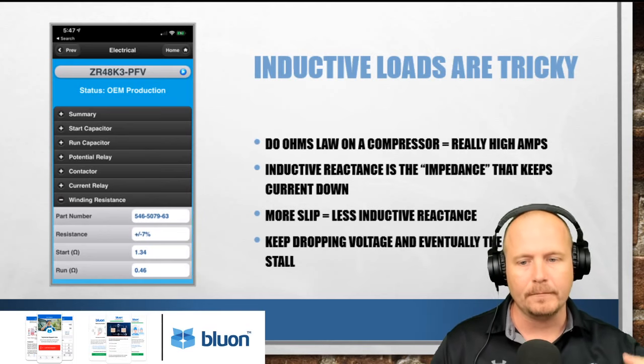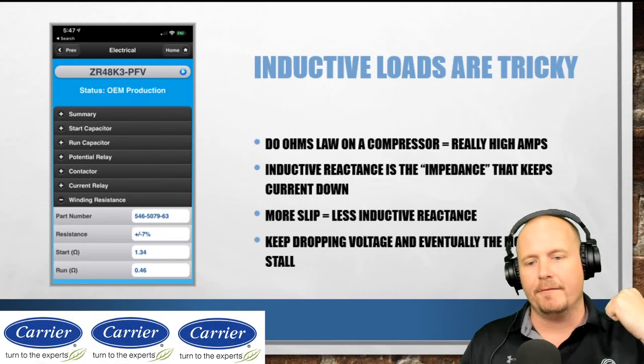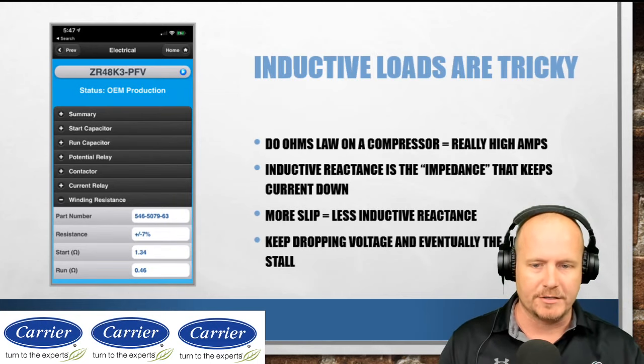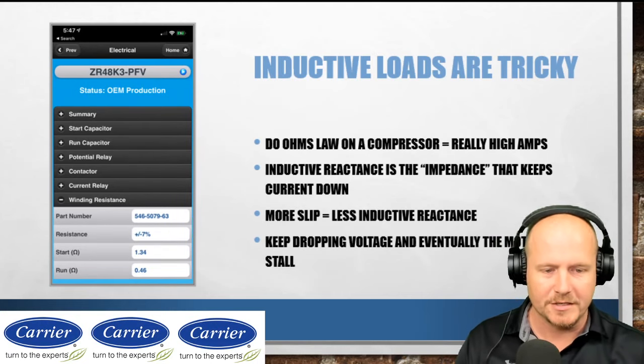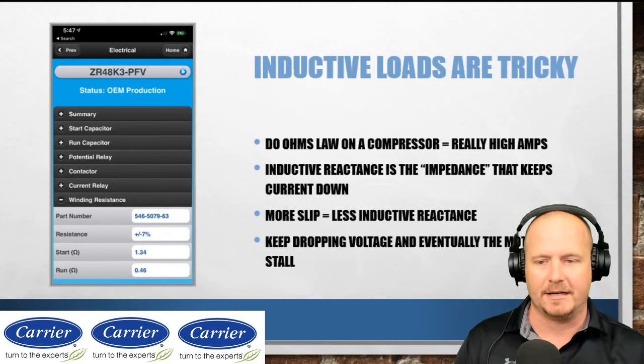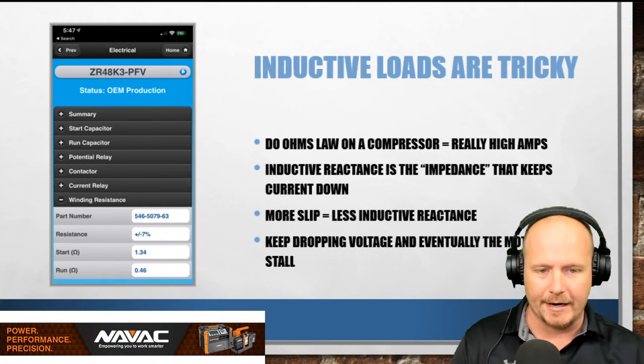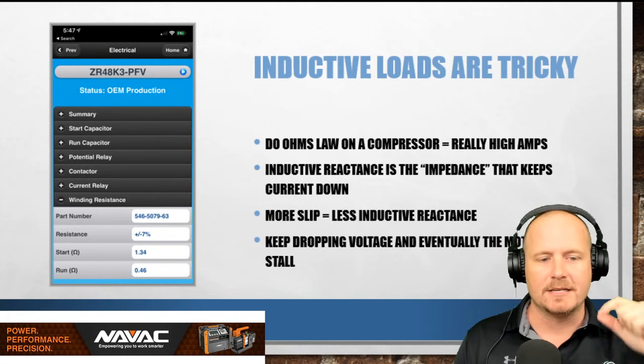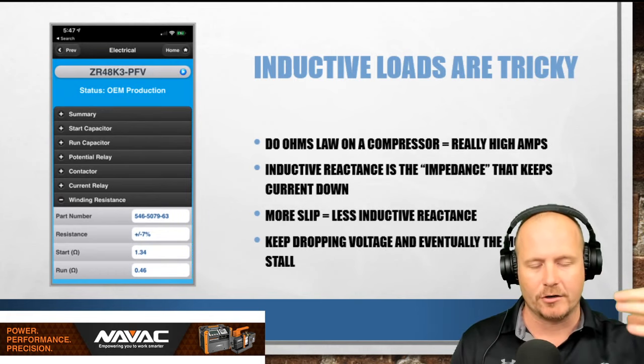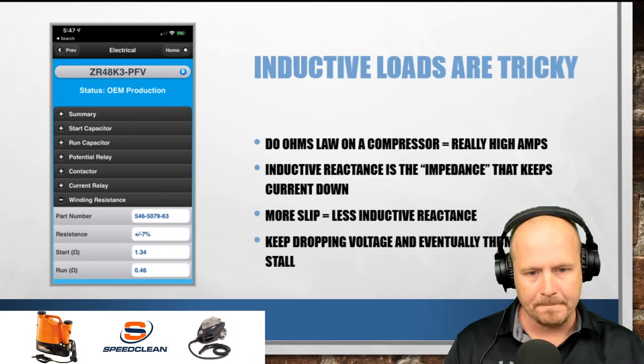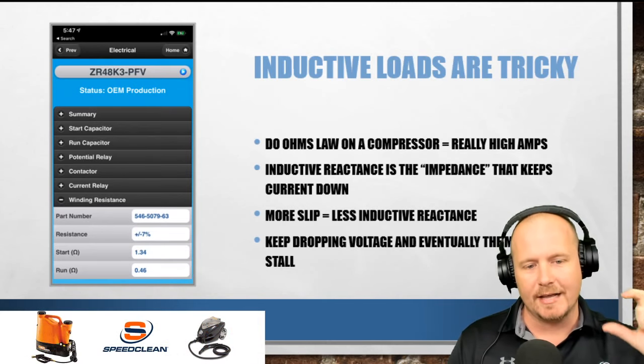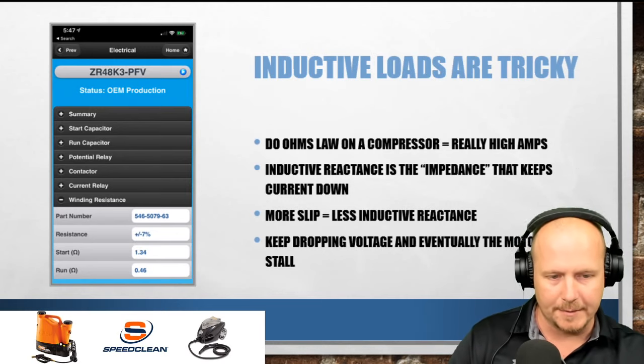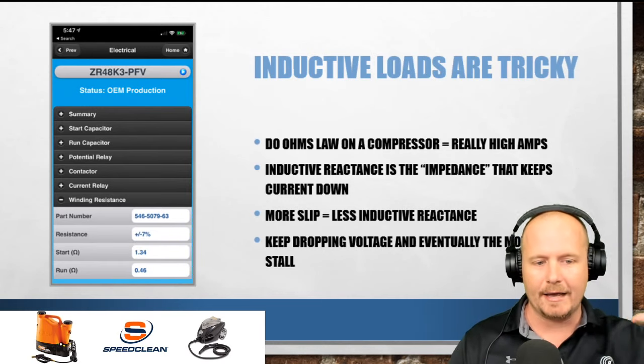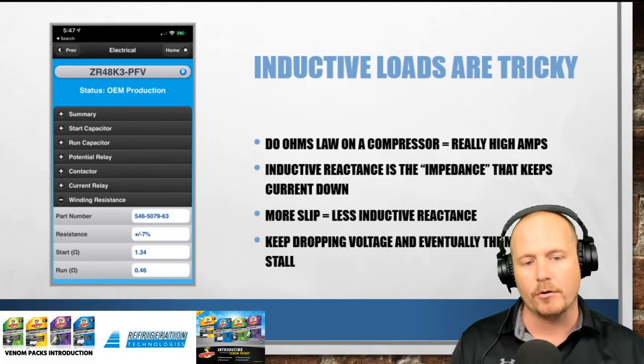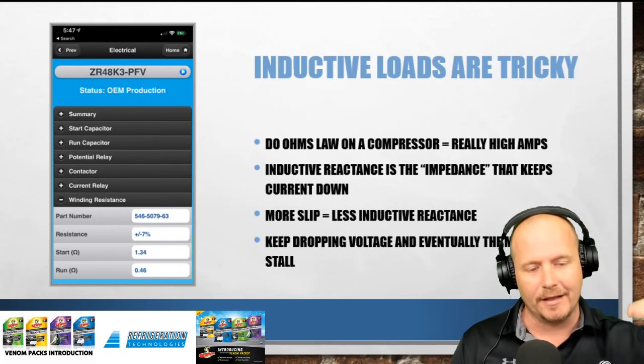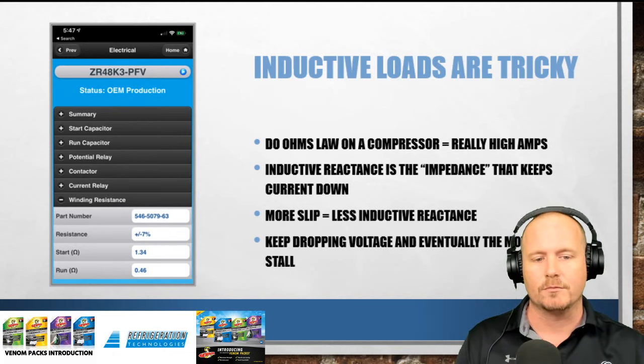So what that means is that if we were to just do Ohm's Law on a compressor, we would think that the thing would draw crazy high amps. And of course it does for that very first millisecond, that very first cycle. There is high current drawn. Inductive reactance is the impedance, or the resistance that keeps the current down once that motor gets running. More slip equals less inductive reactance. So the more a motor slips, the more physical mechanical resistance there is against the operation of that motor, the higher the current's going to be because you have less resistance. Remember, less resistance equals more current.